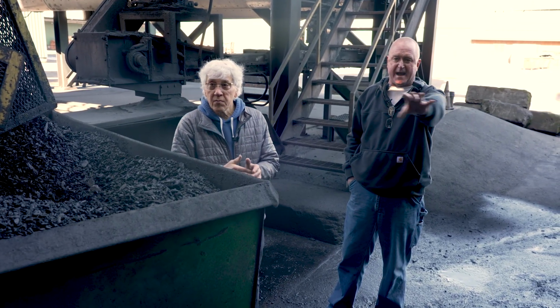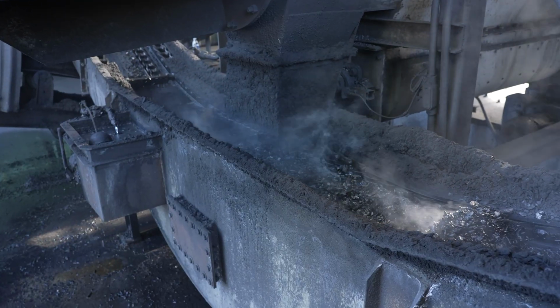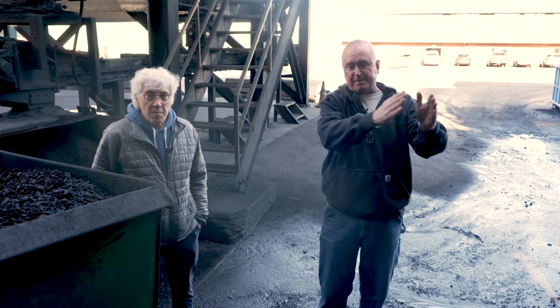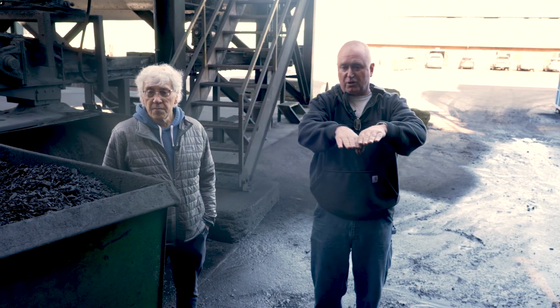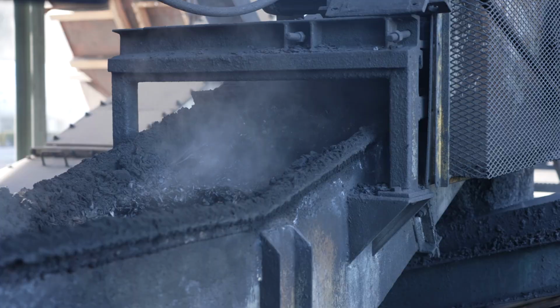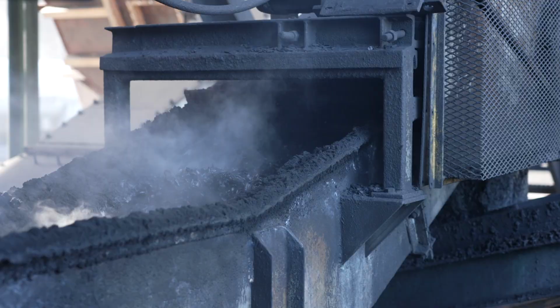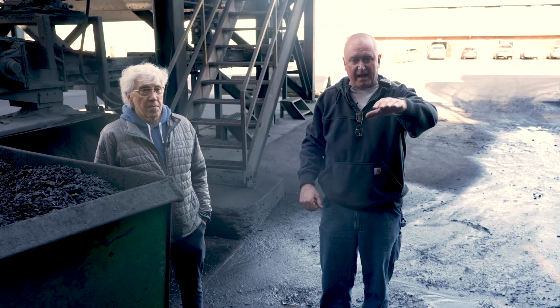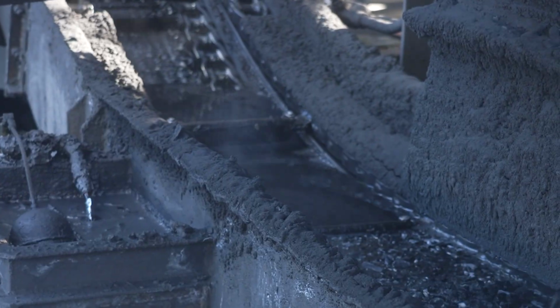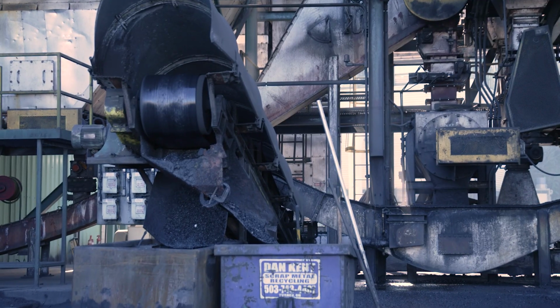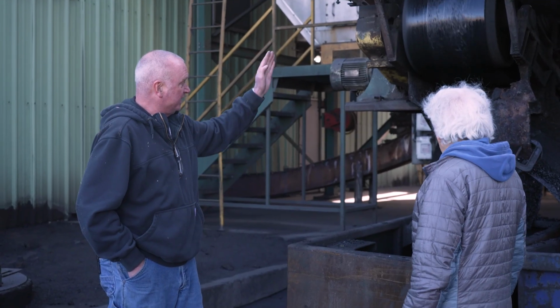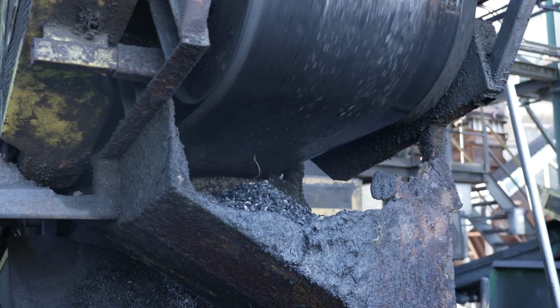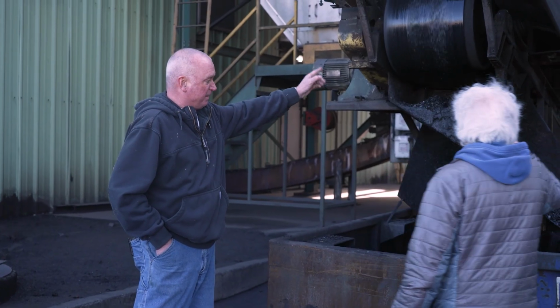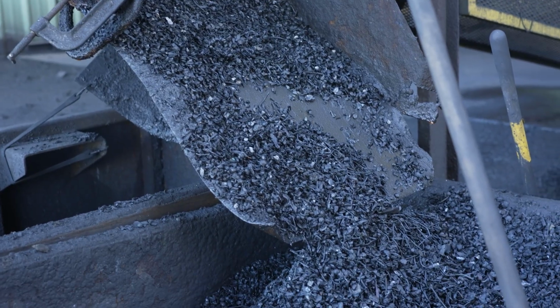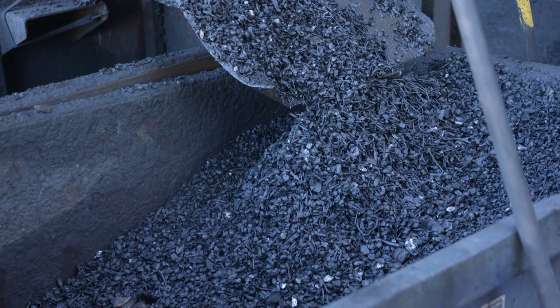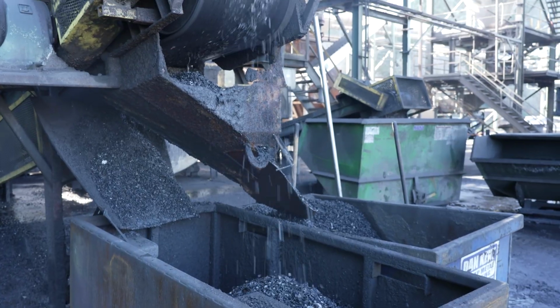Behind you is a water bath. The water bath does two things. It separates the rock and metal from the coarse ash. The coarse ash will float, and the chains will take it to the west and deposit it in this box. The rock and metal is heavy. It sinks and travels this way. Then it goes up a rock belt. In this rock, there is ferrous metal in the way of nails. There is a magnet at the head pulley of this belt that is separating the nails over into a metal bin. And then the rock ash goes into a rock box, which goes out with the waste ash.